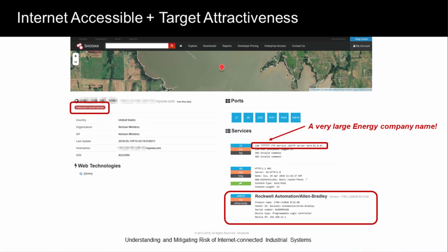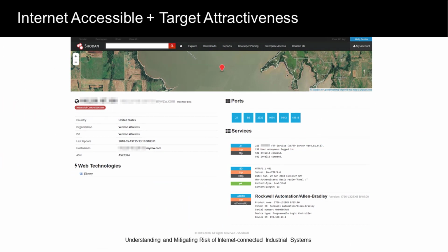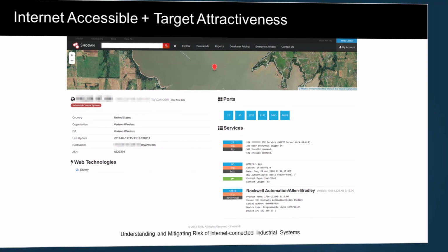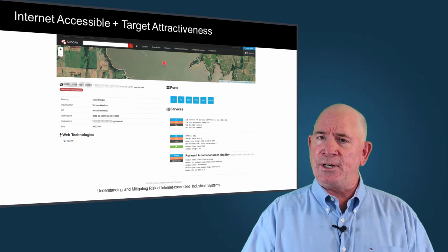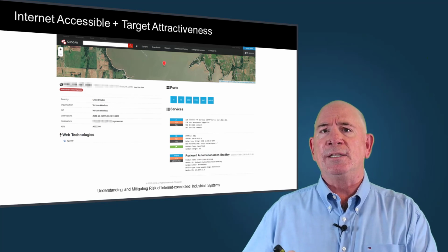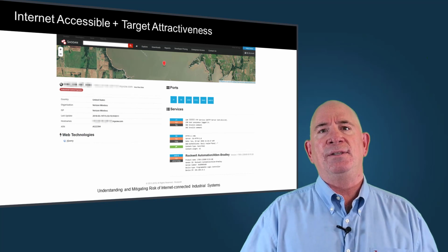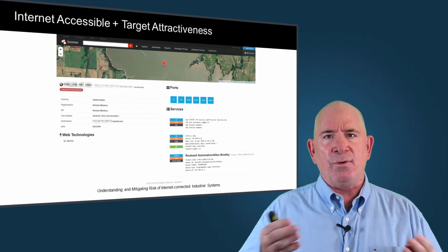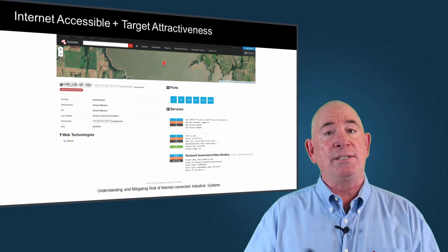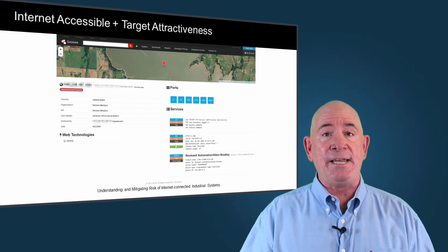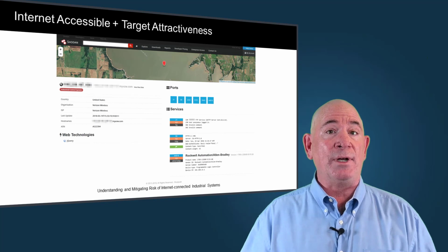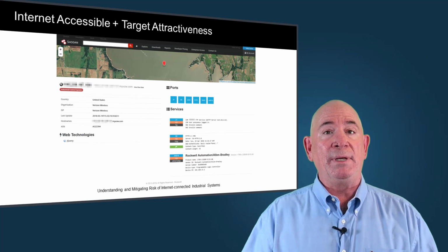Now, this is a little bit disturbing because Shodan is able to see those ports and services, which means there doesn't appear to be any security mechanisms between the PLC and the Shodan services. So of course this triggered a response protocol where I was then called in to start doing some investigation and take a look at exactly what happened and what could be remediated.